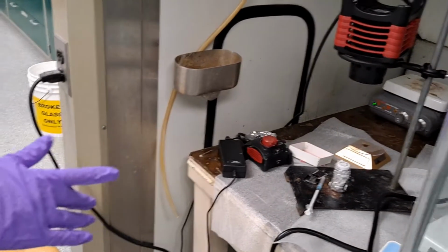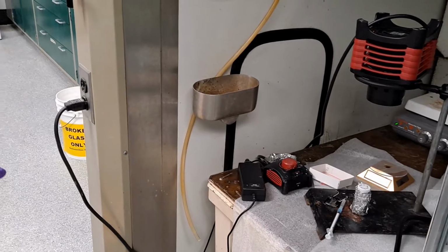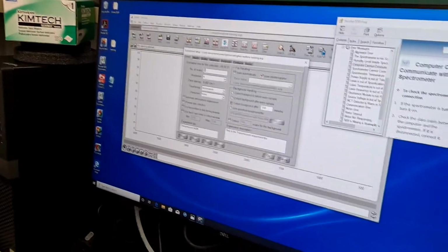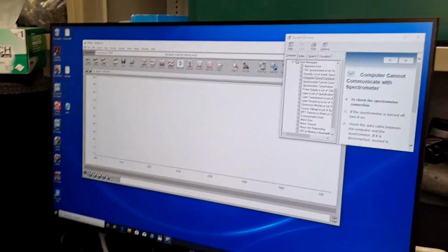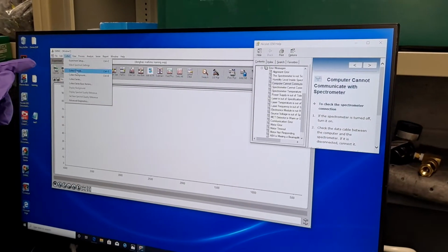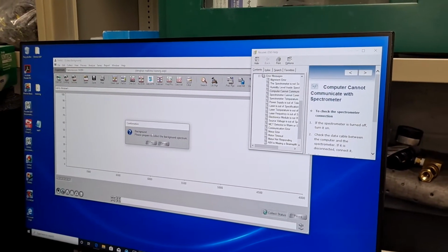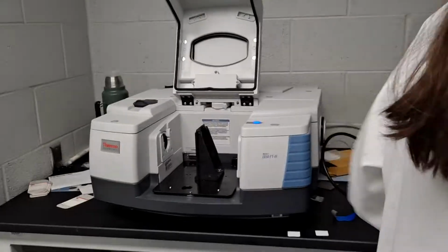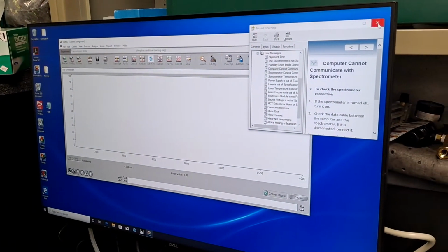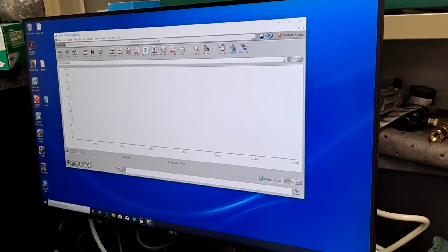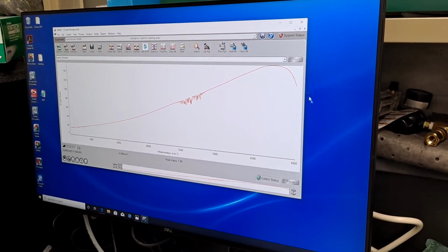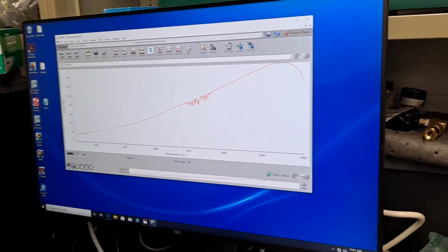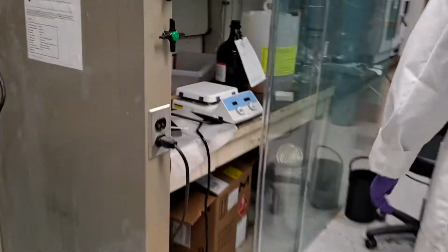Background check, and you can just run the background, fill the sample, and then put that in. Okay. Here is your setup again. You'll go to collect, experiment setup. Make sure this is on 32. Hit OK. Then you'll hit collect again. Collect background. Since the UV experiments have the lid up, we'll do the background also with the lid up. So collect background. You can see it's counting the number of scans, and you get this very generic ambient atmosphere background curve. So we'll collect that.